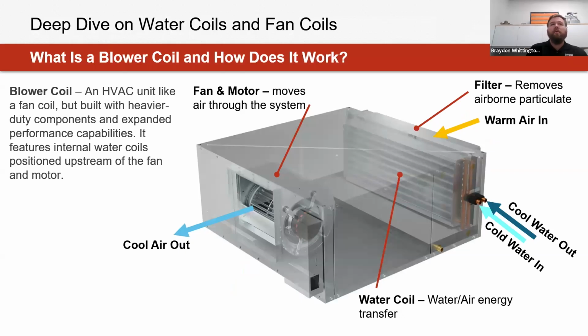The other form of equipment we might see, which I like to visualize as the bigger brother of a fan coil, is a blower coil unit itself. Commonly, in terms of difference between blower coils and fan coils, it also has a motor. It does also have a coil, but a lot of the time these are configured in a draw-through configuration. So you have air being drawn in through a coil from a fan before it's delivered to the space for a blower coil, and vice versa for a fan coil pushing air across the coil.